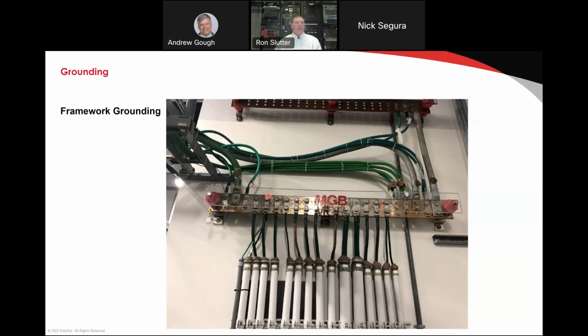Also, when we're doing grounding, we need to have in and out capability. This particular bar only has 2 holes, right? What we really need is a bar that has 2 holes in the bottom, 2 holes in the top to allow current to come into the bar and be absorbed. So we have producers and absorbers. Producers and absorbers can't be on the same side of the bar. On this side of the bar, we have producers and absorbers. So if this is a producer and this is an absorber, if this produces 100,000 amps of lightning current, that 100,000 amps is going to be induced in this conductor right here. Okay? And so this becomes a choke. This will not allow that current to flow out, even though it's an absorber.